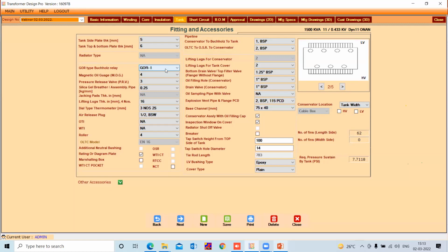drawings, everywhere. You can see here the tank side plate thickness, top bottom plate thickness. Based on that, your 3D diagram will generate automatically. Then other drop-down options like OTI, WTI, marshalling box, additional neutral bushings. So all these drop-down options are available to select or choose fitting and accessories as per your customer requirement. Here also the option is available to choose cable boxes, either both side or LV side only.